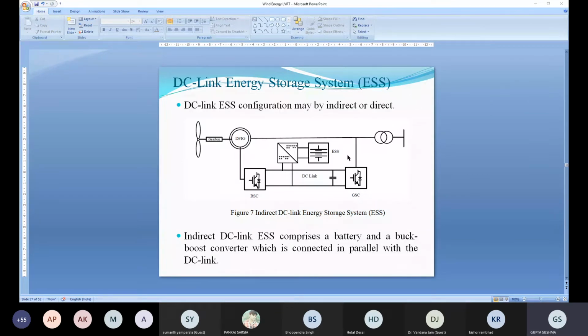So if there is a high voltage, that energy is converted and stored in the energy storage system. If there is a low voltage, then it will supply the reactive power and feed it to the grid, so that the grid voltage recovers fast. So this is the DC link energy storage system.